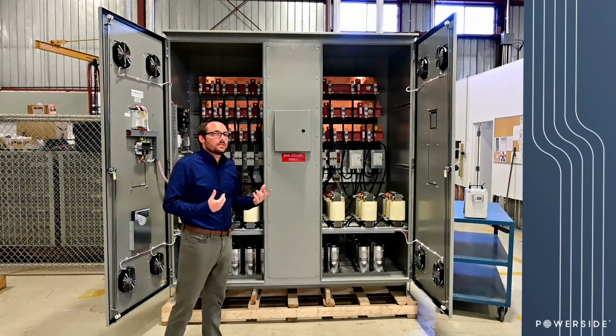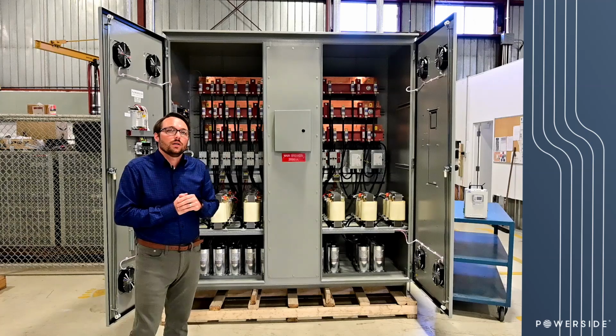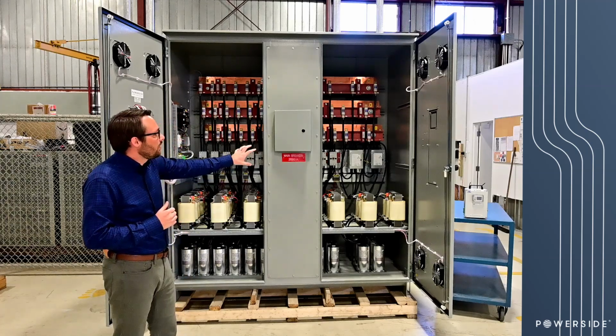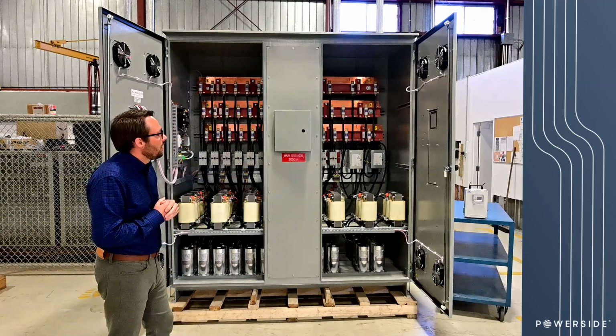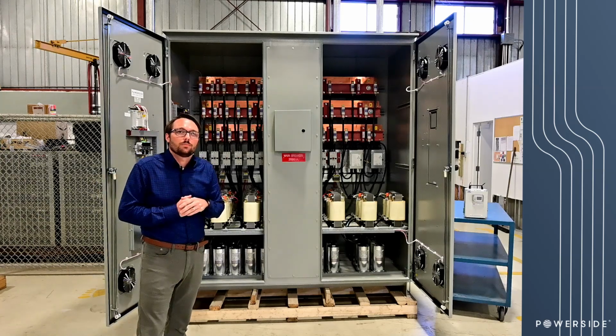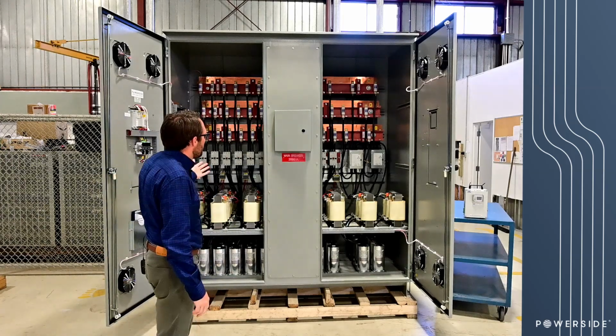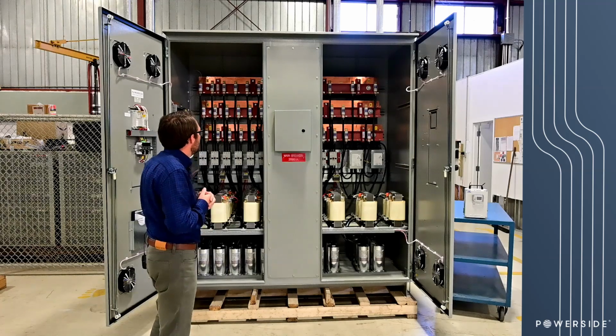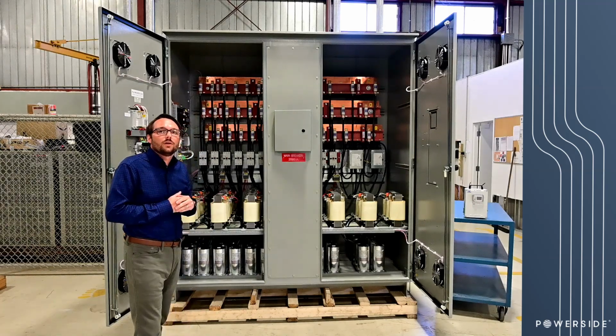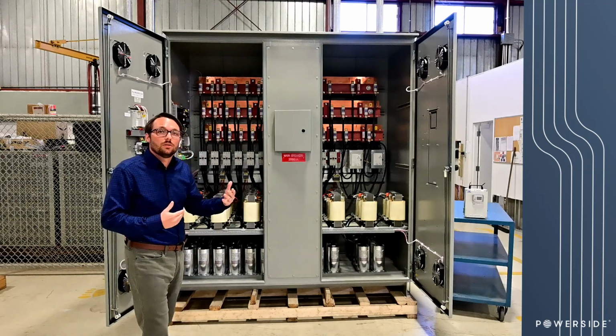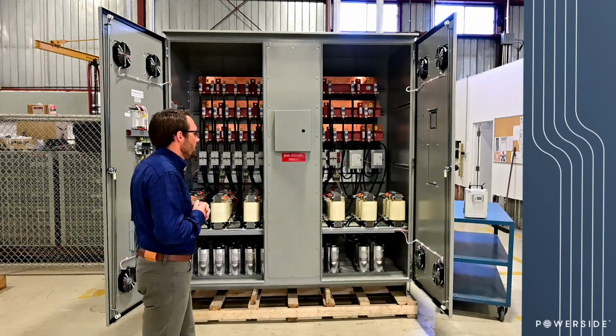And one of the things this is going to help with is we're going to be able to use the thyristors to do all of the fast switching required during the pressing operation, while we're using our contactor base here to correct for the load that is much more stable and much more predictable.